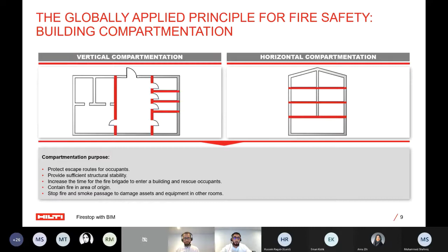In any fire-rated zone, a fire-rated wall will have MEP services and openings passing through it, and these are weak areas from a fire-rated perspective. If I have a pipe, duct, or cable tray passing through the wall, the opening must be slightly bigger than the service itself, for ease of installation. The gap left between the MEP service and the wall is called an annular space. If left untreated and not fire stopped properly, it would allow the passage of fire and smoke.